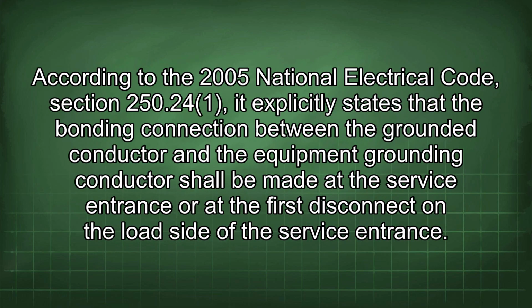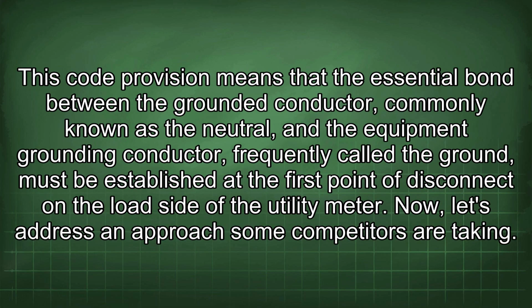According to the 2005 National Electrical Code, Section 250.24, it explicitly states that the bonding connection between the grounded conductor and the equipment grounding conductor shall be made at the service entrance or at the first disconnect on the load side of the service entrance. This code provision means that the essential bond between the grounded conductor, commonly known as the neutral, and the equipment grounding conductor, frequently called the ground, must be established at the first point of disconnect on the load side of the utility meter.